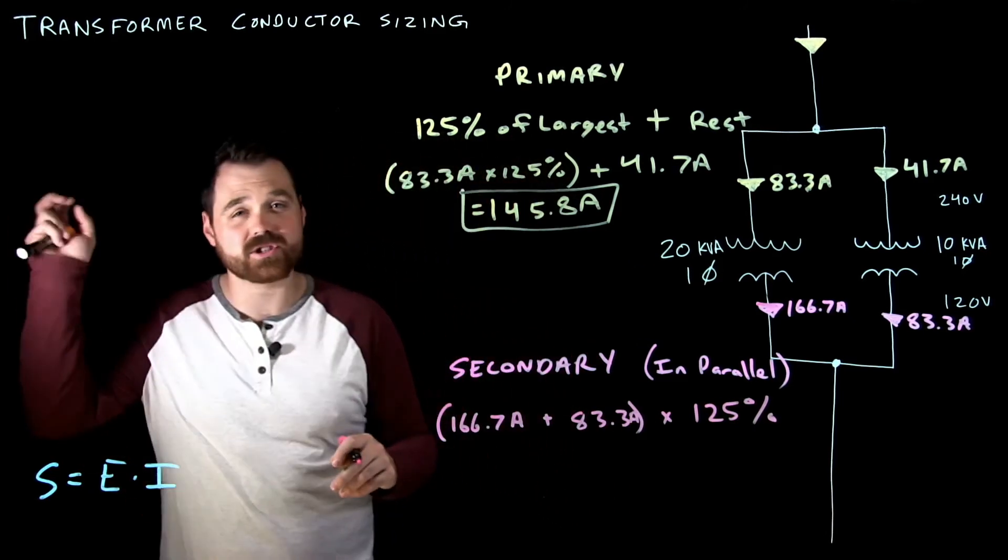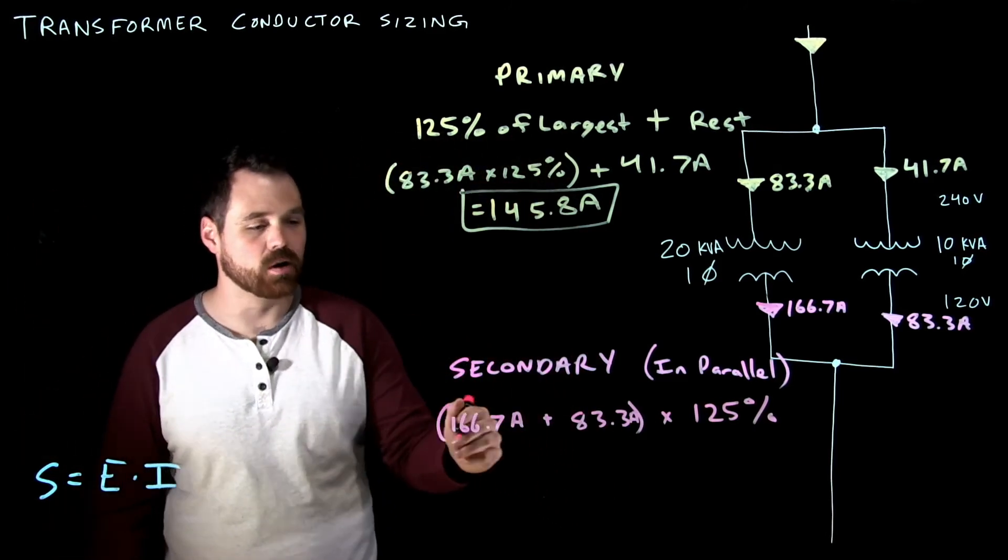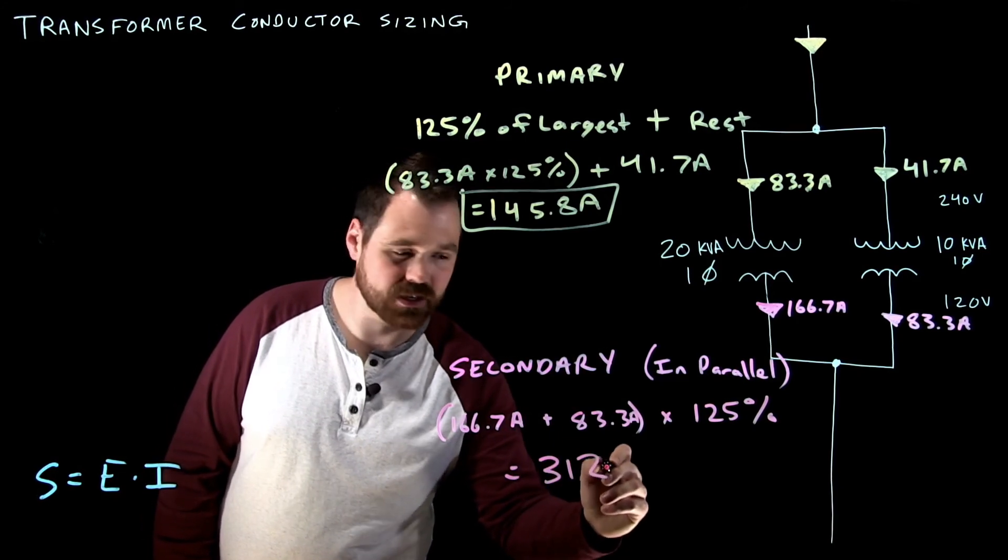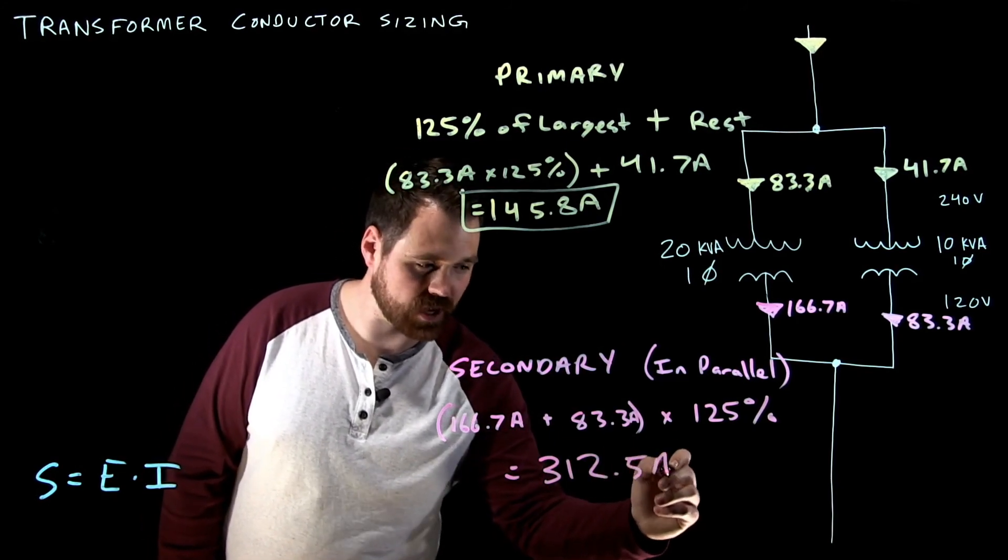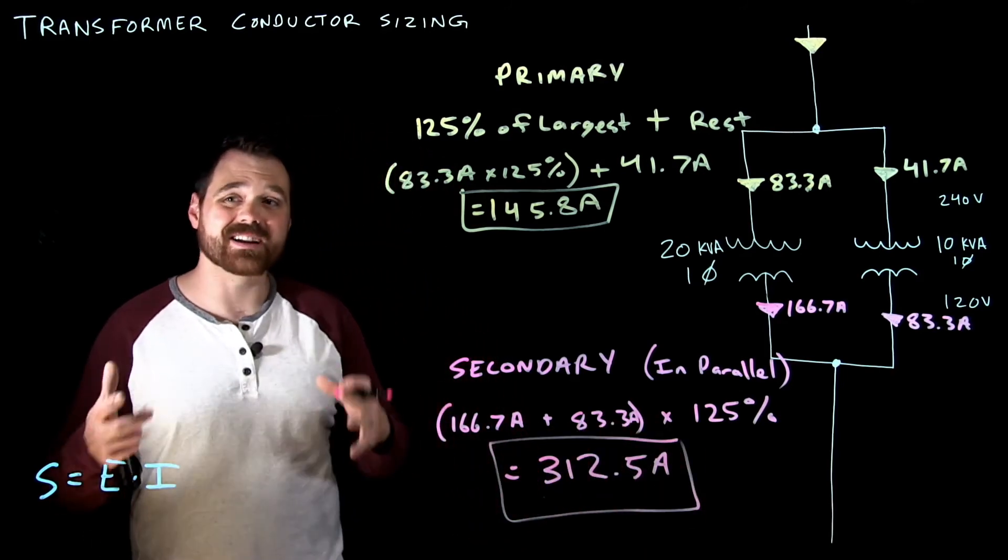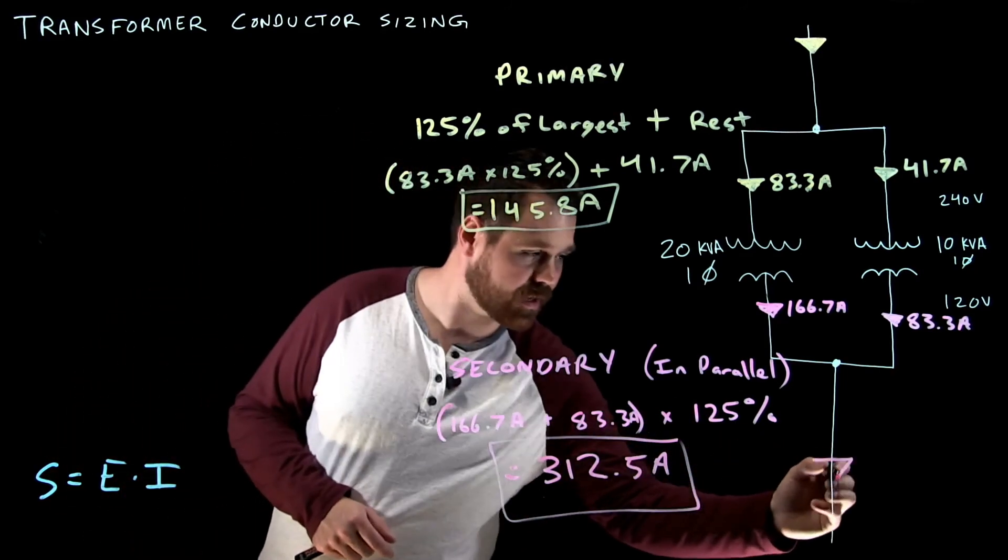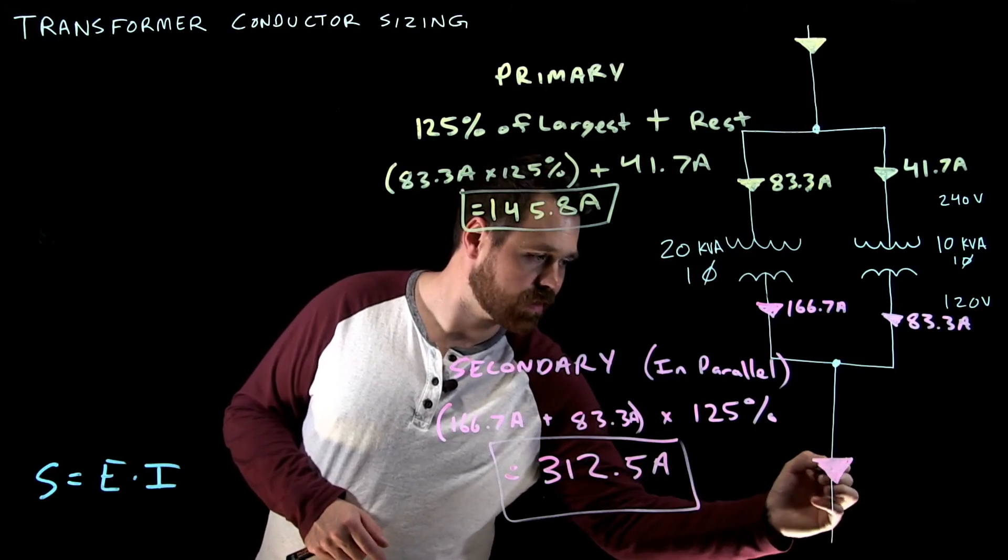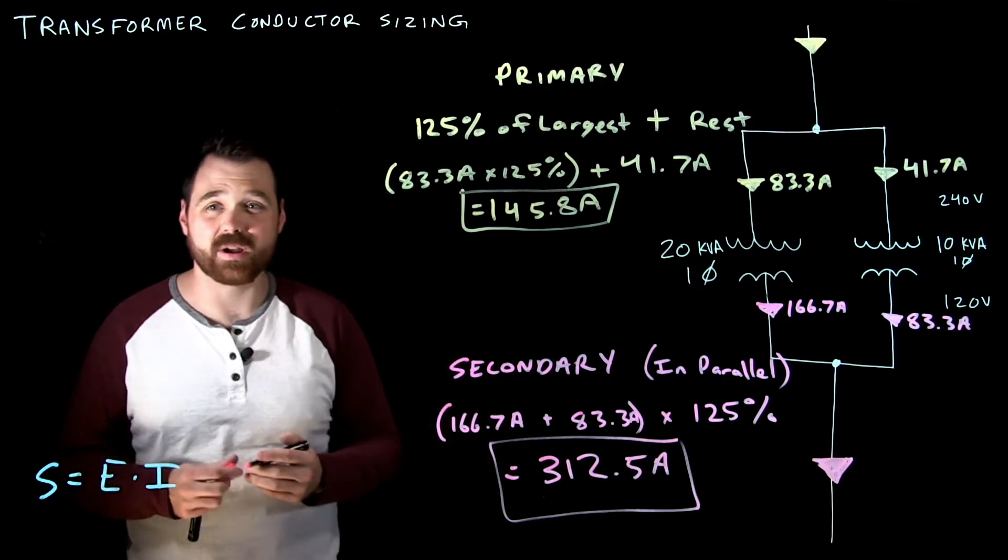And again, you can check out the rules I'm referencing down below. But that gives me a required minimum capacity of 312.5 amps. This number right here is how much current that conductor right here, my paralleled secondary needs to be able to carry.